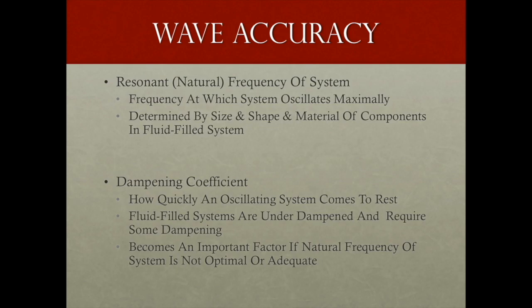Your waveform accuracy is dependent on two characteristics mainly: the resonant, or natural, frequency of your system, and your damping coefficient. The resonant frequency is the frequency at which the system oscillates maximally. It is determined by the size, shape, and material of the components in the fluid-filled system. The damping coefficient is how quickly an oscillation will come to rest.